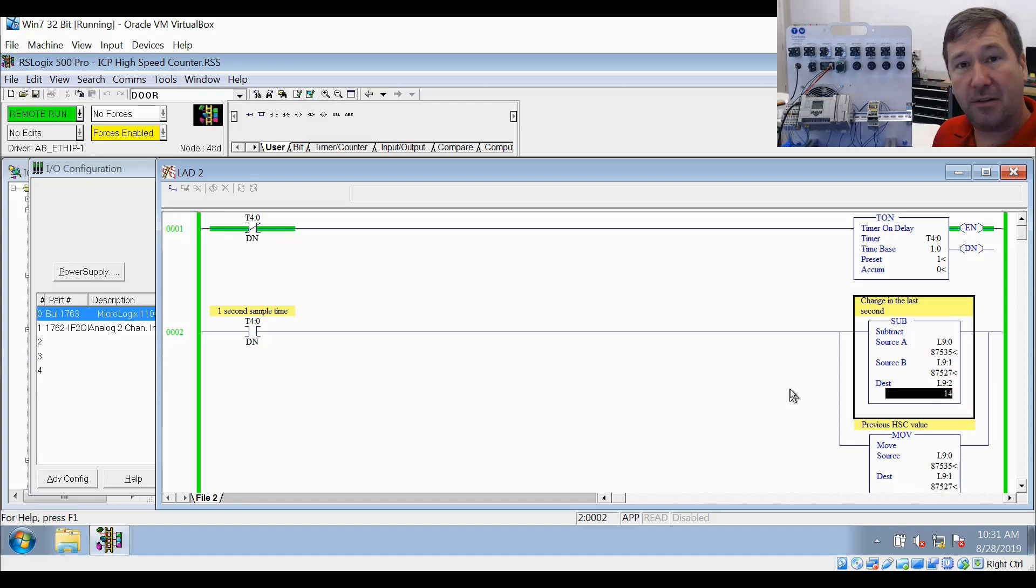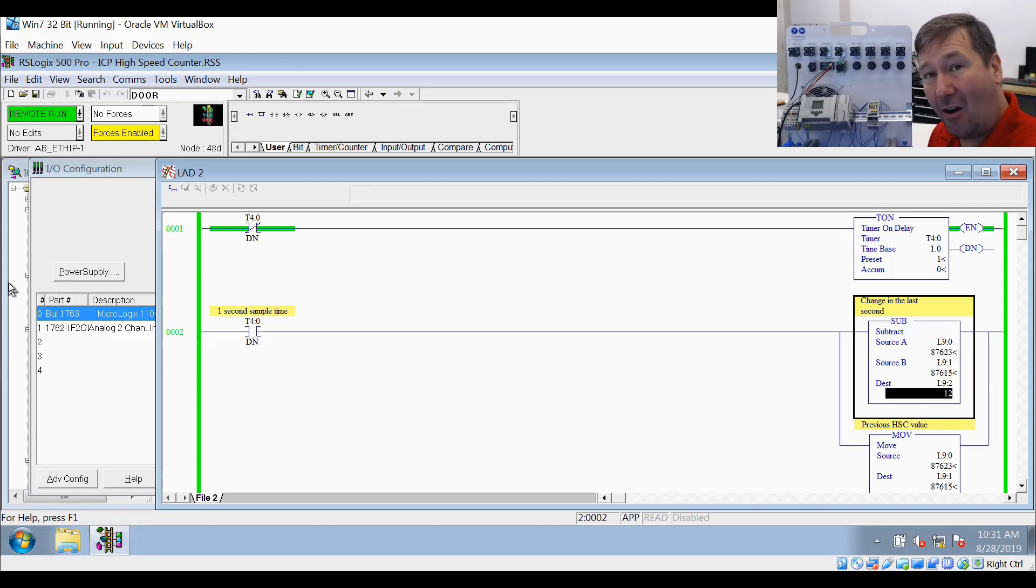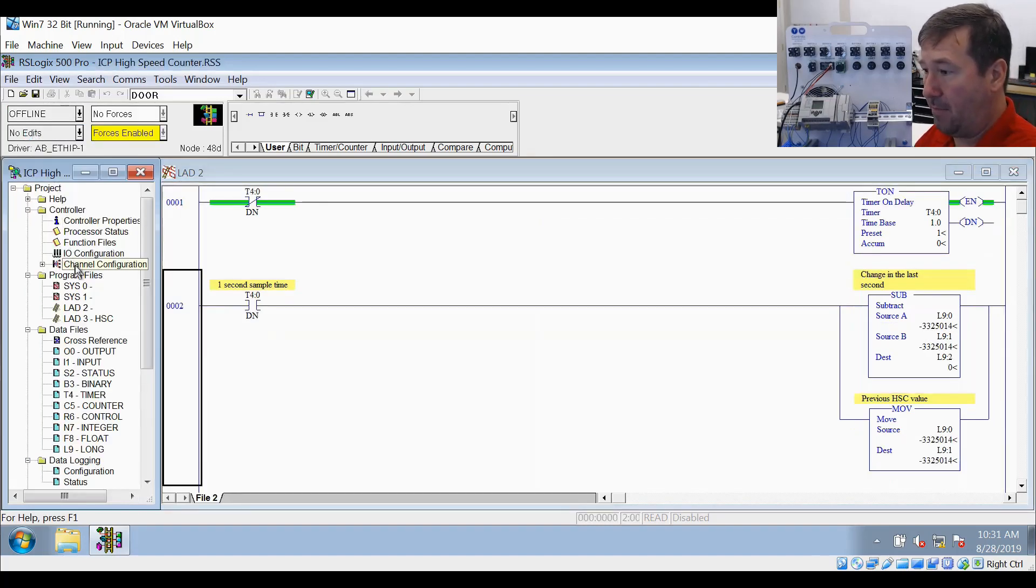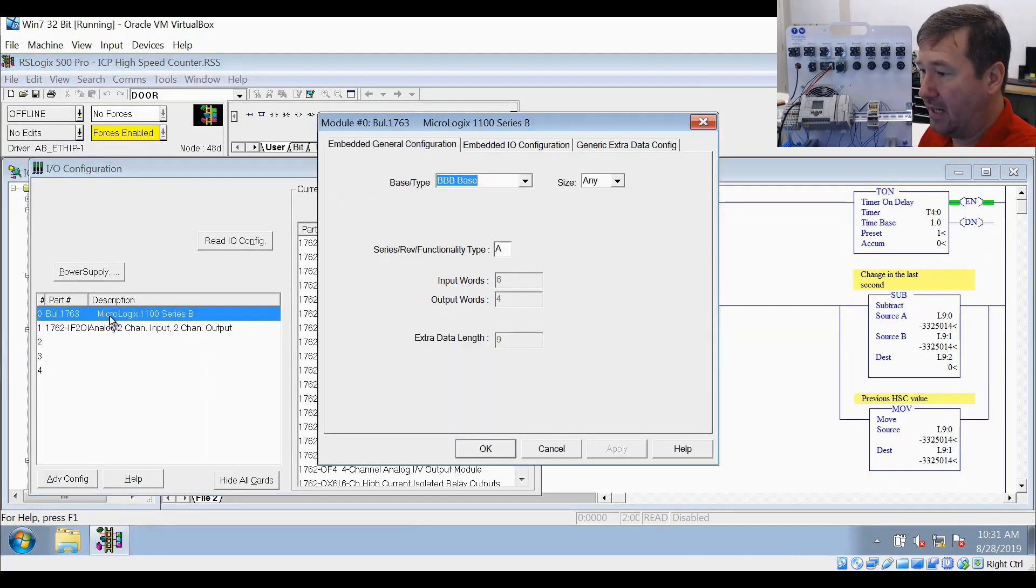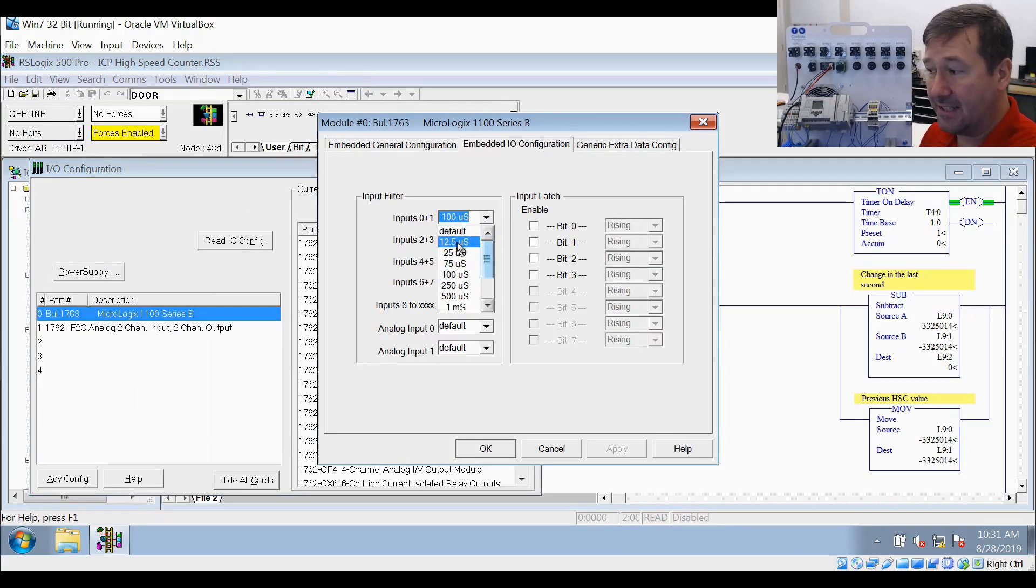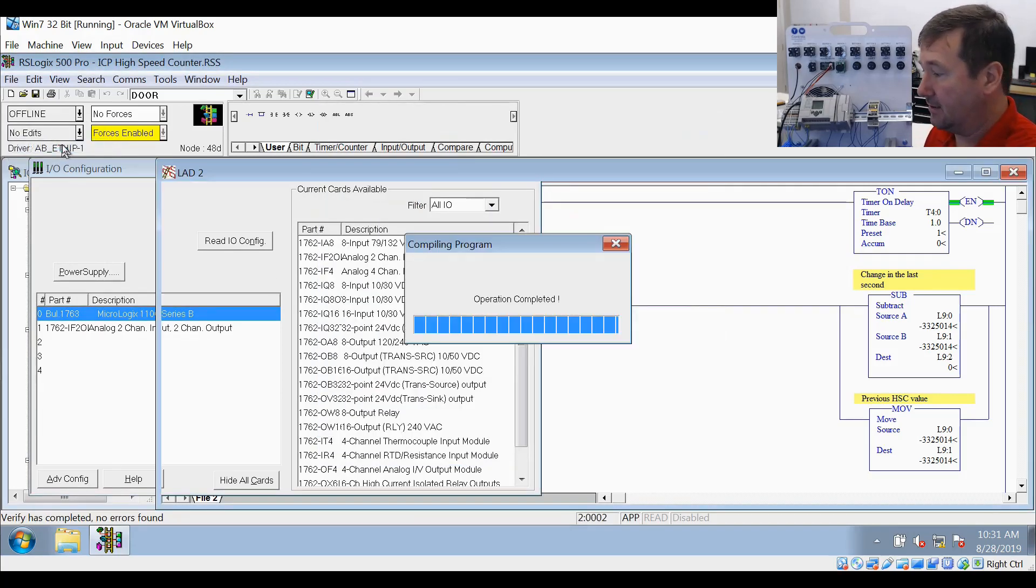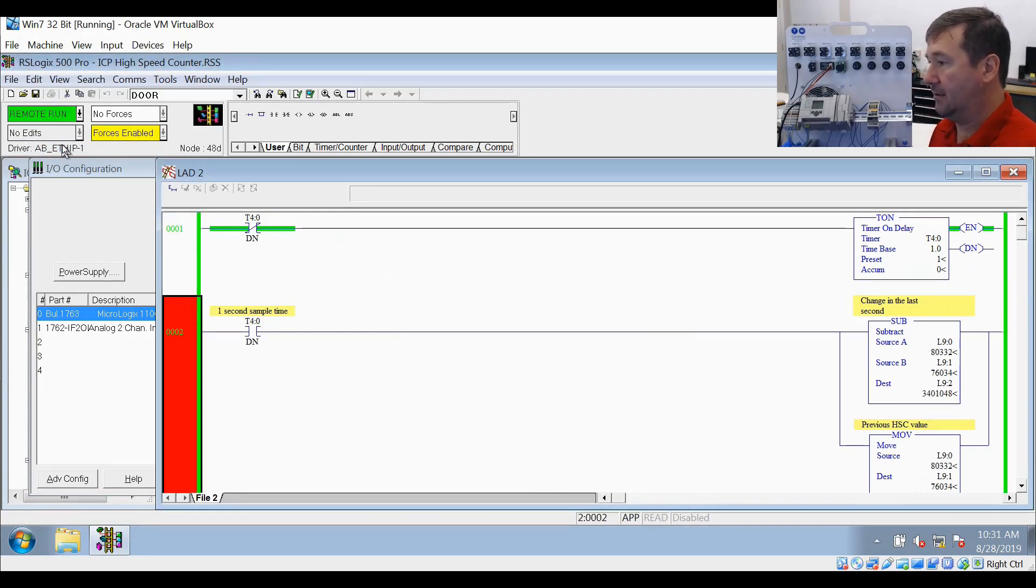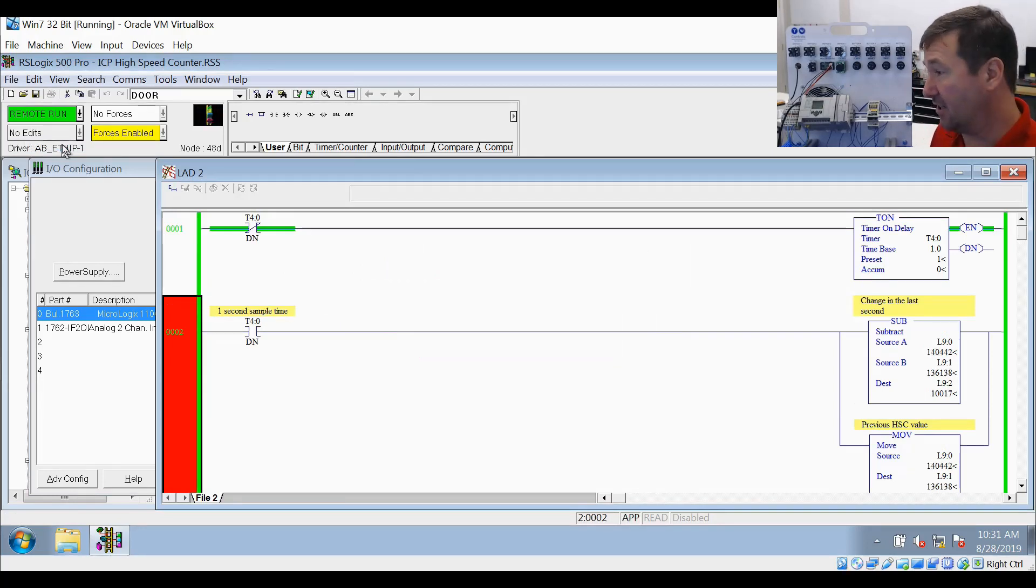Your input filters have to be low enough to let these pulses get through. For me, I always go with the lowest input filter on the high-speed counter and make sure I use the best wiring practices to keep noise out. You may do the math and figure out you could get away with a certain one, but I like to go with the lowest one. So we'll go back one more time to our I/O configuration, slot 0, embedded I/O, and I usually set these at 12.5 microseconds. We'll download that. There you go. Now we're showing roughly 10,000 pulses per second, just like we should.